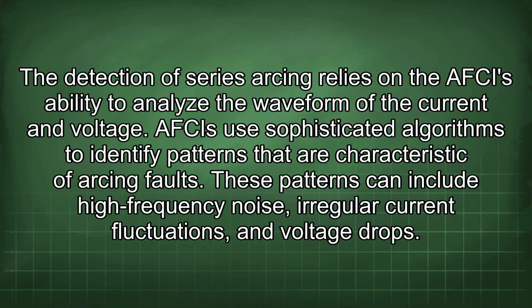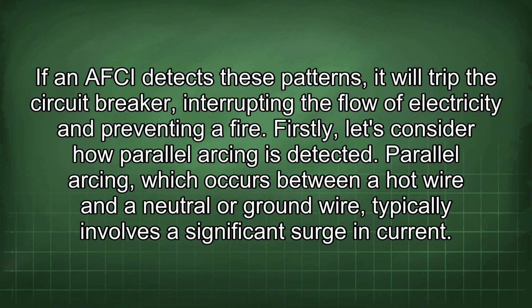The detection of series arcing relies on the AFCI's ability to analyze the waveform of the current and voltage. AFCIs use sophisticated algorithms to identify patterns that are characteristic of arcing faults. These patterns can include high-frequency noise, irregular current fluctuations, and voltage drops. If an AFCI detects these patterns, it will trip the circuit breaker, interrupting the flow of electricity and preventing a fire. Firstly, let's consider how parallel arcing is detected.